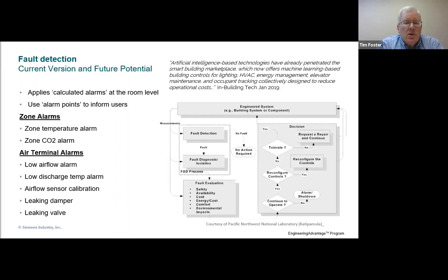Whereas fault detection is more proactive in trying to identify, looking at all the variables on HVAC, lighting, other building functions, looking at all those variables in a kind of deep data mining way, trying to figure out those interconnecting relationships, and then identify things that ordinarily would be difficult to see unless a trained operator was specifically looking for it. Like a damper that wasn't working, or maybe a valve that was leaking, but you wouldn't know that because something else in the system was wasting energy, but it was compensating for a leaking valve.